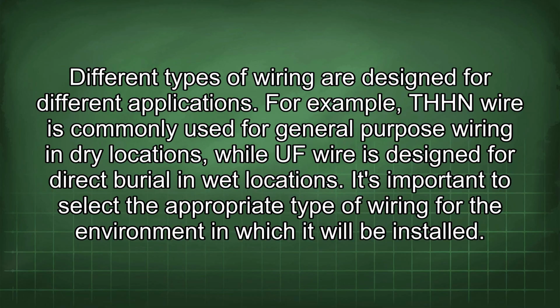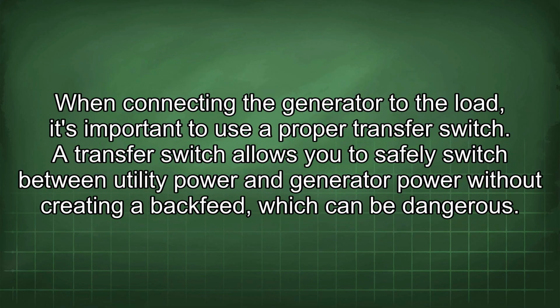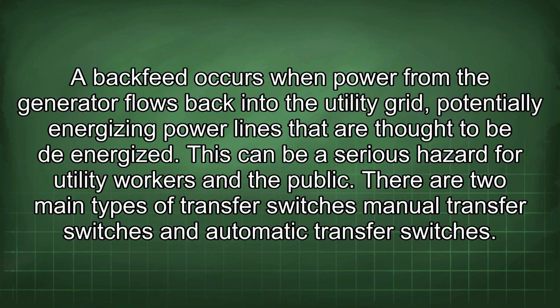It's important to select the appropriate type of wiring for the environment in which it will be installed. When connecting the generator to the load, it's important to use a proper transfer switch. A transfer switch allows you to safely switch between utility power and generator power without creating a backfeed, which can be dangerous. A backfeed occurs when power from the generator flows back into the utility grid, potentially energizing power lines that are thought to be de-energized. This can be a serious hazard for utility workers and the public.